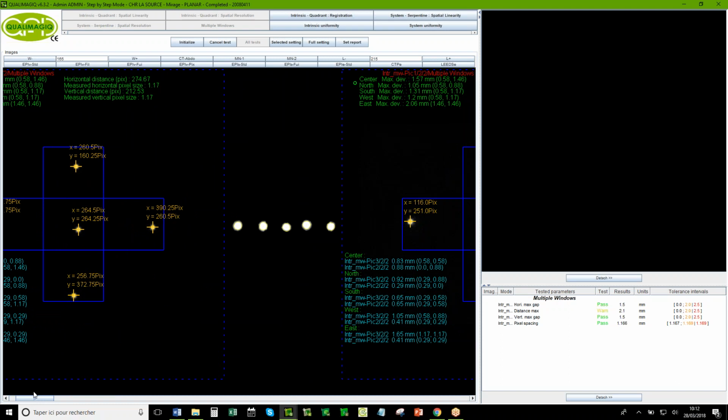Just a quick question. Is it necessary to have 2 energies, because we really use mostly only technetium? You are not obliged to do this test. It's very important. If you use only technetium with your camera, of course, this test is not necessary.